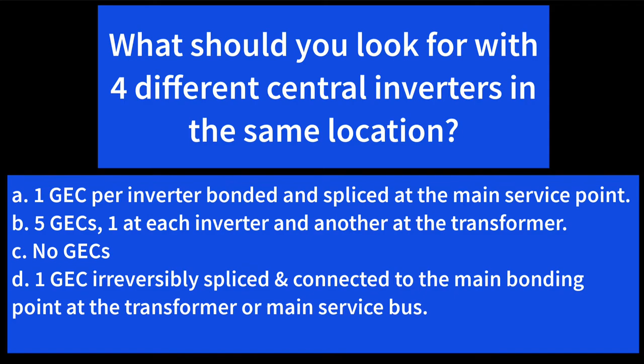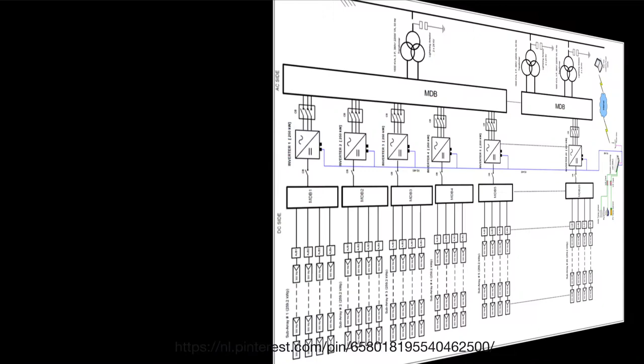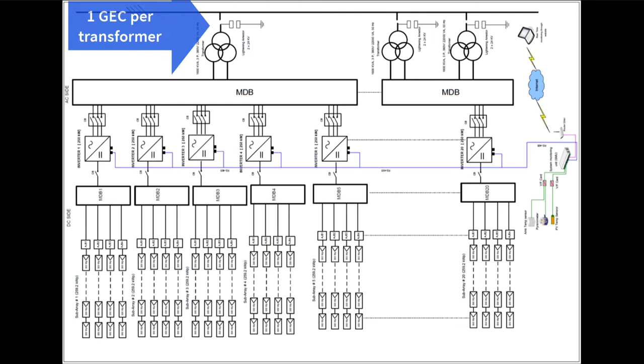If this is a dedicated service for a PV system, and let's say each one of these are 1 megawatt inverters, and they're all coming together to a 4 MVA transformer or something like that, then the transformer is going to have a GEC. Not the inverters. And so that's where they're probably wrong. So I would say D would be correct, is that there'd be 1 GEC irreversibly spliced and connected to the main bonding point in the main service panel, if there is a main service panel, because there may not be. There could be just a connection to the transformer.